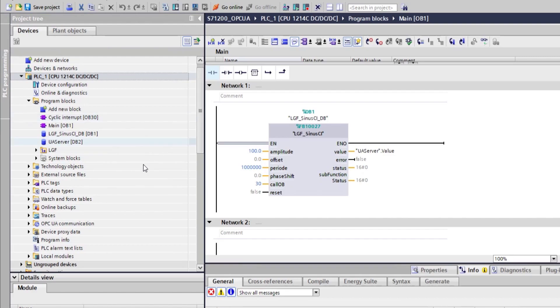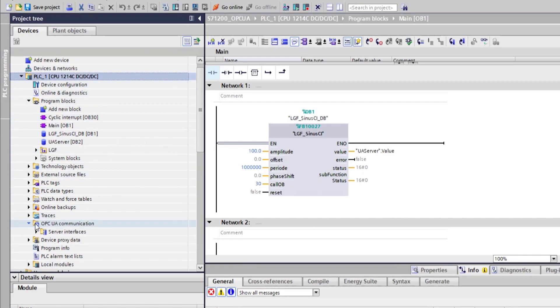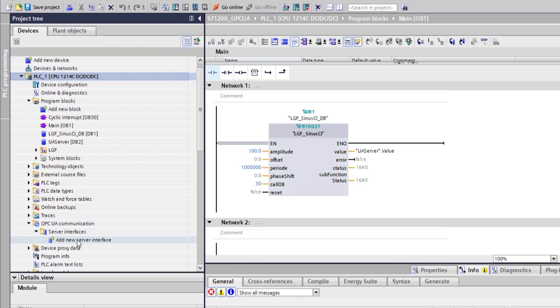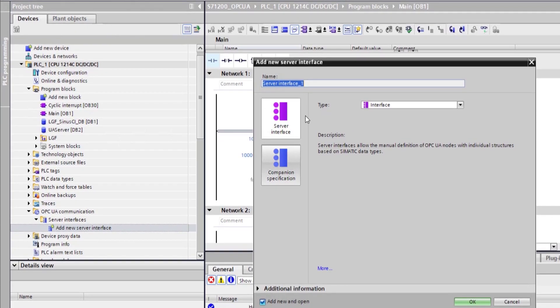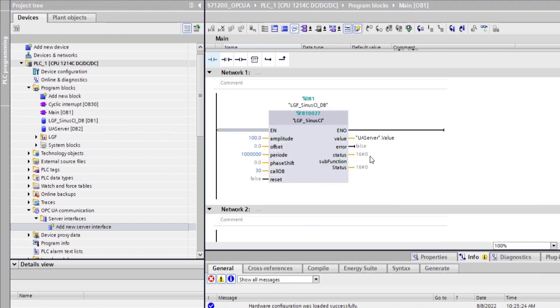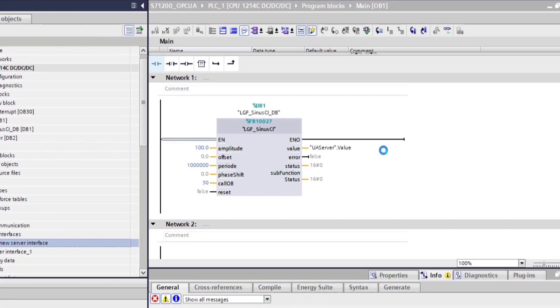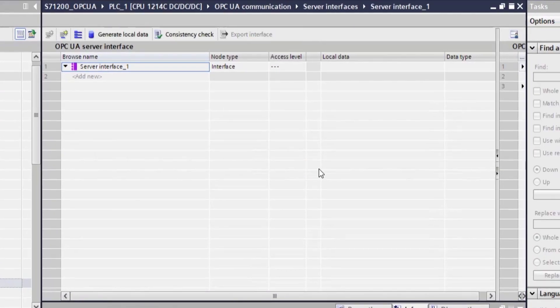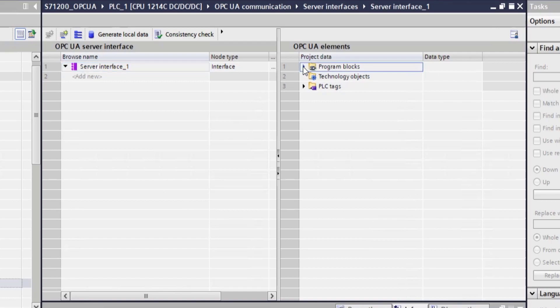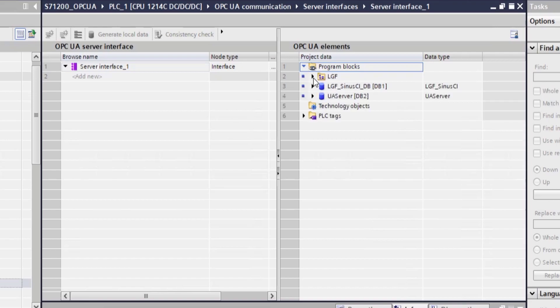So server interfaces can be found on the left hand side here under OPC UA communication. So if we go under server interfaces and add a new one, we can then select a server interface type interface. And then a new window opens. And this window, if you grab this here in the middle, it allows us to basically drag and drop tags that we are interested in. So whatever you want to expose on OPC UA, you just select from here, from the right hand side.